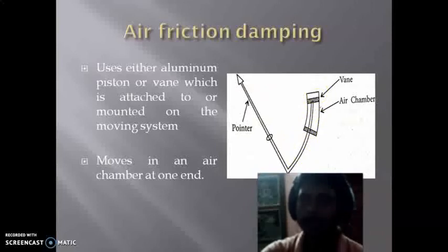And due to the movement of the pointer at its final position, due to this pressure developed in the air chamber, the vane attached with the system will not move into its final position, and it will basically restrict the vibration. So this kind of arrangement is very effective, and we use it in any kind of indicating systems or indicating instruments.